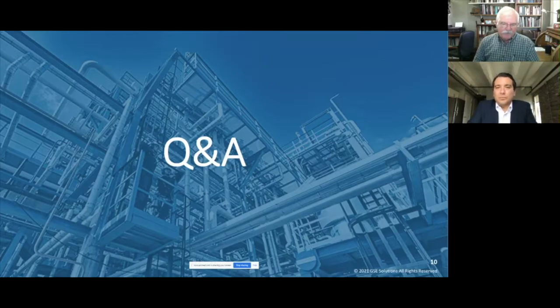Obviously you're a slave to the instrumentation that you have, and one way you can try to achieve more redundancy in the models is to add physical relationships, because there's two forms of redundancy, right? There's basically hardware redundancy, where you have multiple measurements of the same thing. And then there's functional redundancy, which is where you're connecting things through physical relationships, physics, like correlations.